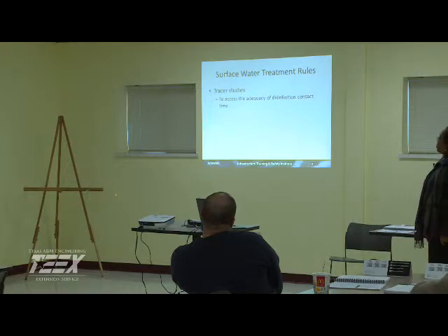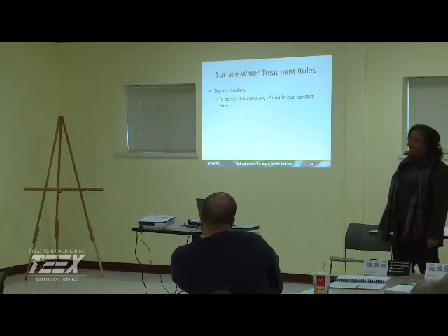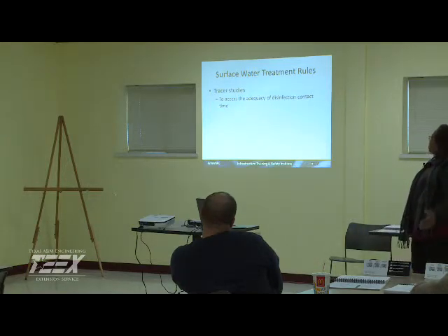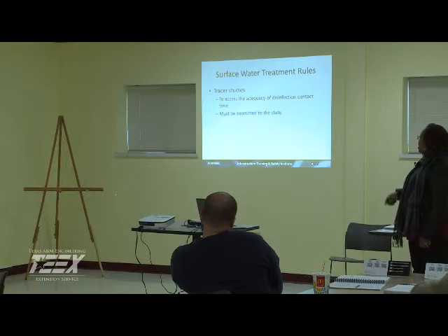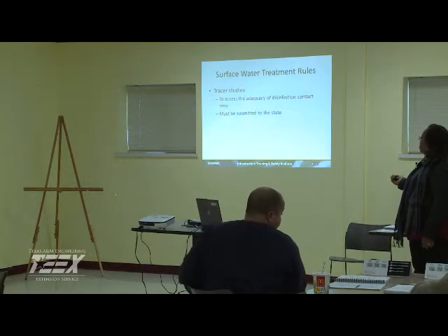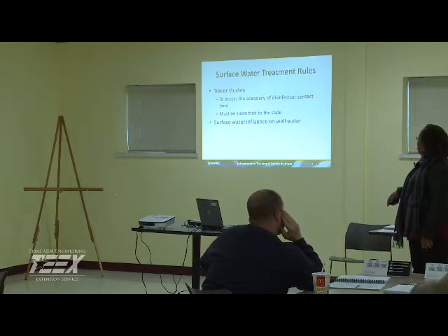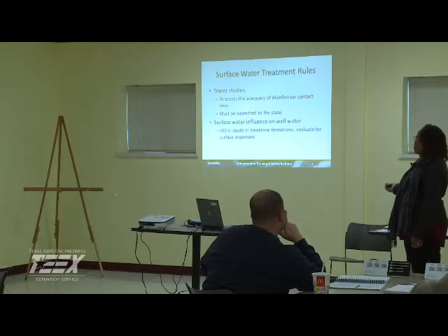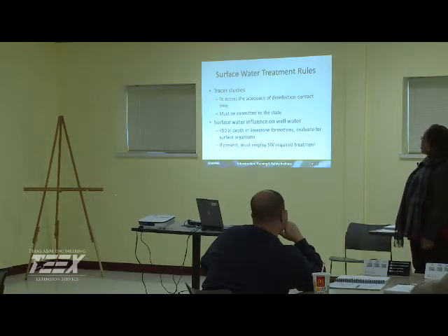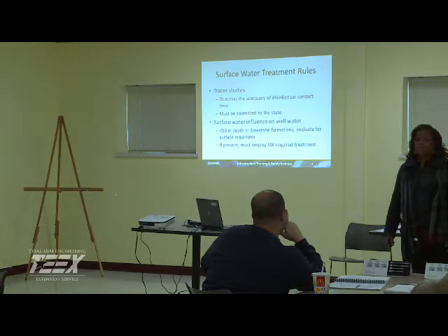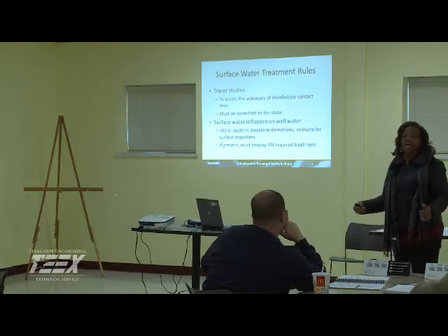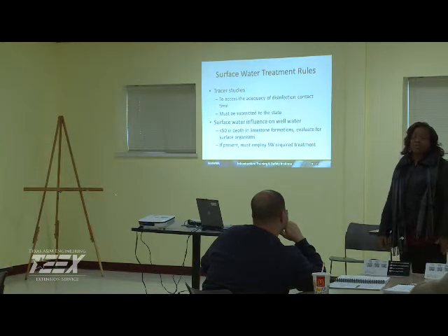You may have to set up tracer studies to assess the adequacy of your disinfection contact time, and you want to make sure any studies like that, you submit that information to the state. If your surface water is influencing your groundwater or well water, again, you want to evaluate for surface organisms, and if present, then you have to step it up a notch and start the treatment that is required for surface water.